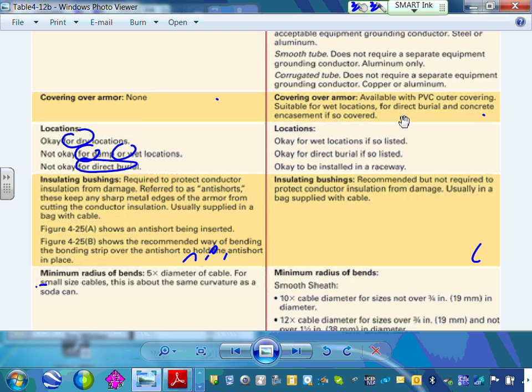So when you put a cable in the ground, in addition to being rated for wet location, it also has to be rated to handle the agents in the ground, the chemicals that can destroy the insulation. Am I making sense? You can have a cable rated for wet location but not for direct burial. Anything underground has to be for wet location, but direct burial, it depends. If it's listed, it can be installed in a raceway for physical protection.